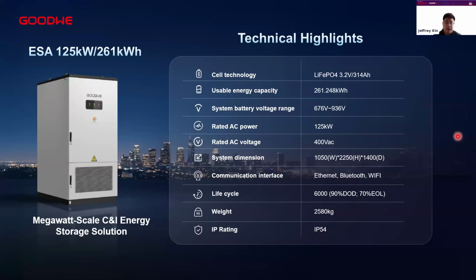Our company's PCS solution is similar to an all-in-one solution, because the PCS is integrated together with the battery. Each cabinet provides 125 kilowatts of PCS and 261 kilowatt-hours of battery. To extend the power capacity of the whole system, you can just double or multiply the number of cabinets.